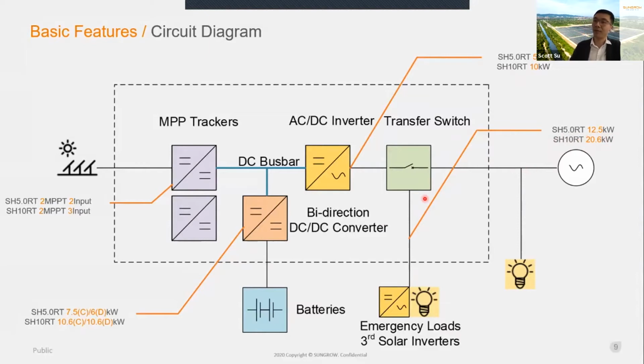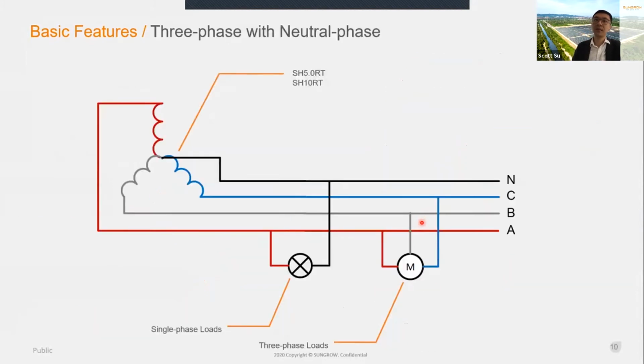So what's the meaning of this capacity? Such as SH10RT is 20.6 kilowatt, so you can install up to 10 kilowatt emergency loads plus up to 10 kilowatt third-party solar inverters. Okay. So the next one is we have 3-phase with a neutral phase. So under the backup mode or off-grid applications, we can supply the 3-phase loads. Also, we can supply single-phase loads.